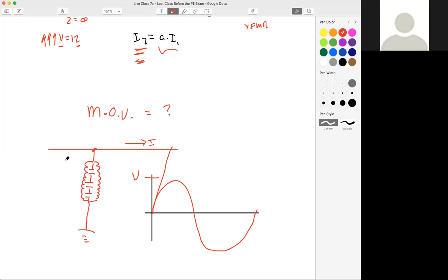Our metal oxide varistor, we'll say that's each of these here. Here's an MOV, here's an MOV, here's an MOV. Each of those close, right? When there's a big enough voltage transient, a voltage spike, when our voltage surges in value really fast, they're going to shunt and create a path directly to ground.